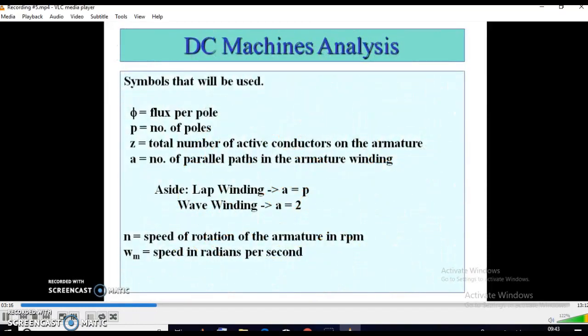Now, the symbols we are using here: phi for the flux per pole, Z for the total number of active conductors, A is the number of parallel paths. In DC machines, for lap winding, the parallel path is always equal to number of poles P, and for wave winding, parallel path is equal to 2. Small n denotes the rotation of the armature in RPM. Omega m is the speed in radians per second.